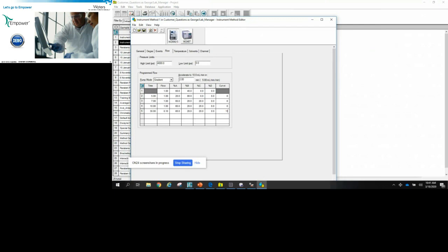So every 10 minutes I'm making an injection, the clock gets re-zeroed, but because I'm stopped on fault due to a SysSuit failure, there's nothing that can trigger that clock. It doesn't re-zero. It keeps recording time. When it hits 30 minutes, and only when it hits 30 minutes, it would then lower the pump flow rate down to 0.1 or 0, but I would be careful about that if you're using any buffers. So, a rather long answer to what is a fairly important question about interactive system suitability.